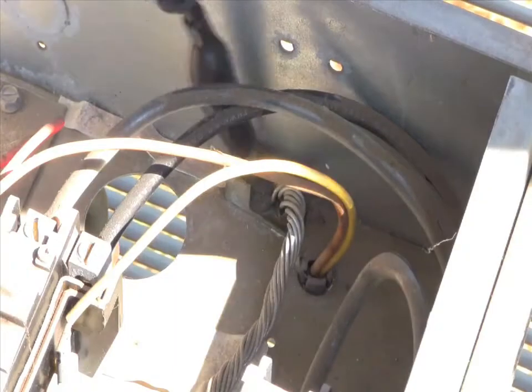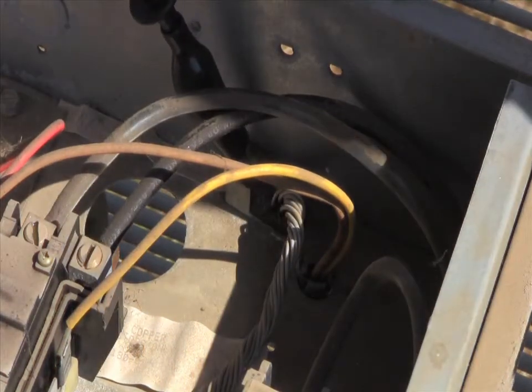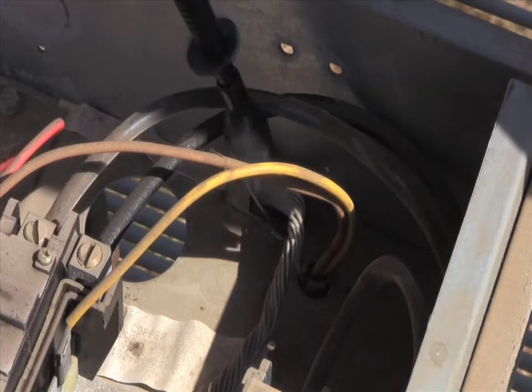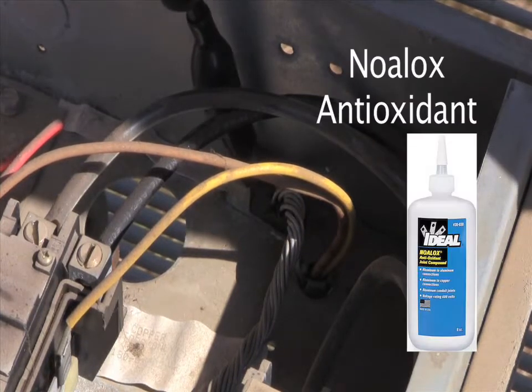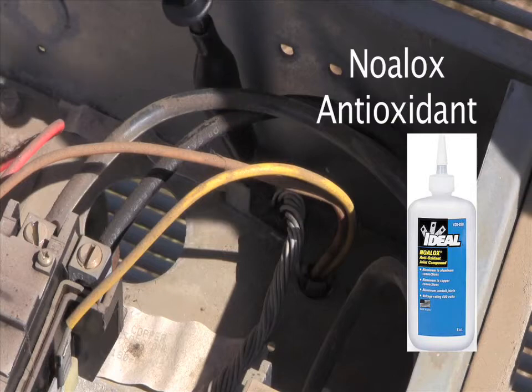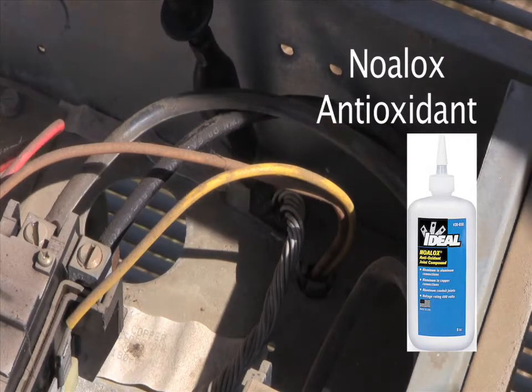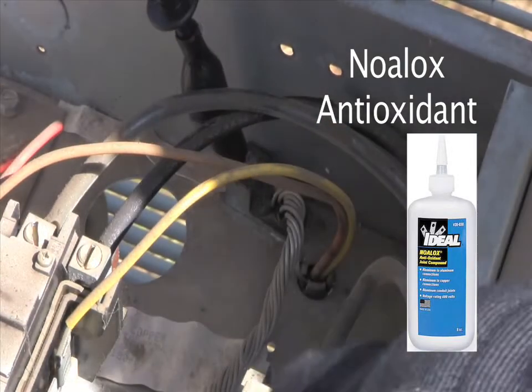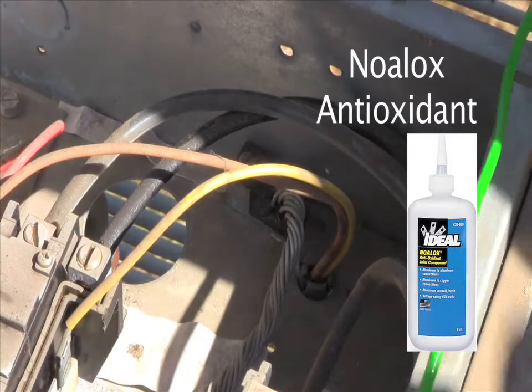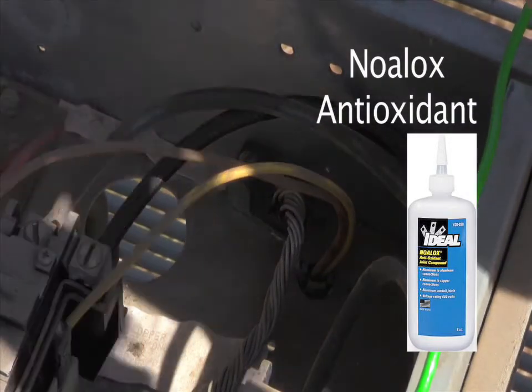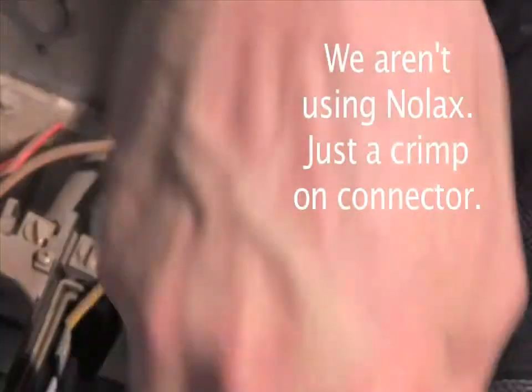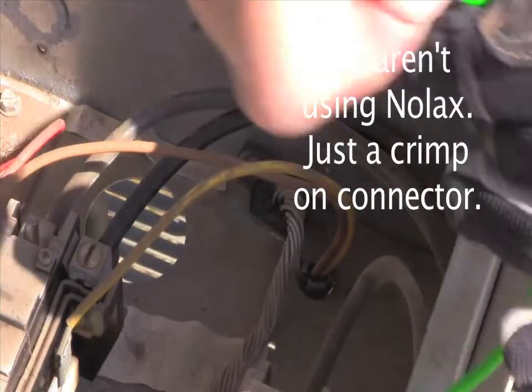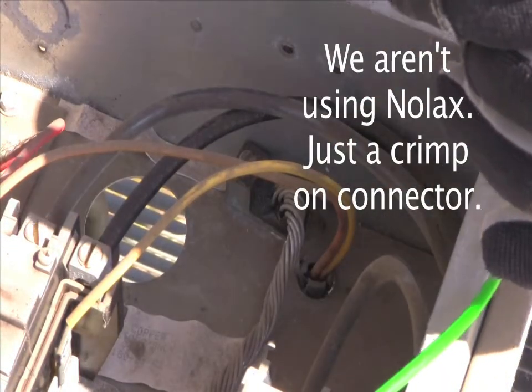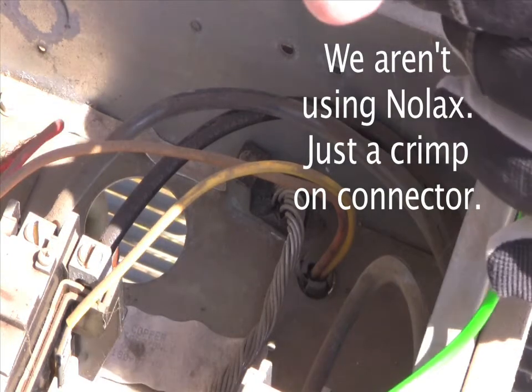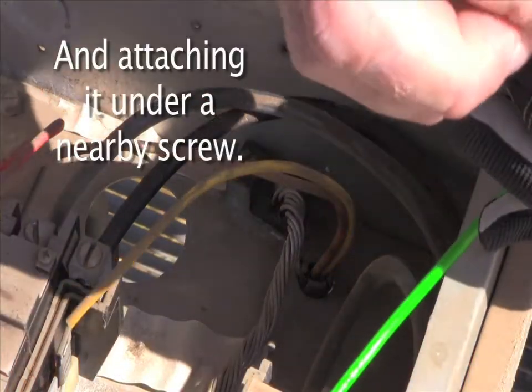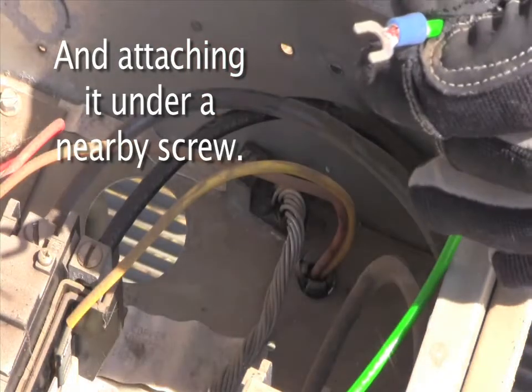This right here is the ground, where the ground gets strapped in. This is an aluminum ground, and that's an aluminum strap. So the only way that you can put this copper and this aluminum together in this strap is to use what's known as Noalox. So I'm going to strip off some of the insulation on there. I'm going to put on this connector, push it through a little bit, and then we're going to crimp it.